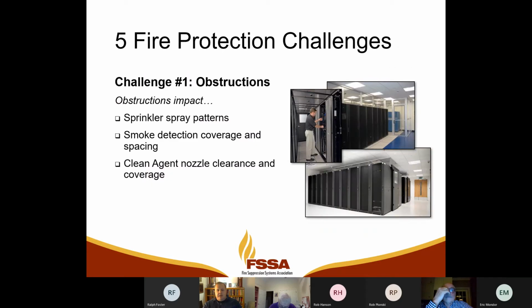So, some of the challenges that these units create. We're going to talk about the challenges, and then talk about what the codes, now NFPA 75 and NFPA 76 for telecommunications facilities, say about these things. One challenge is the obstructions, whether they're vertical obstructions or horizontal ones. They can obstruct the sprinkler spray patterns in the room. They can obstruct smoke detection, coverage, and spacing. They can obstruct clean agent nozzles and how the agent is distributed and covers the room.